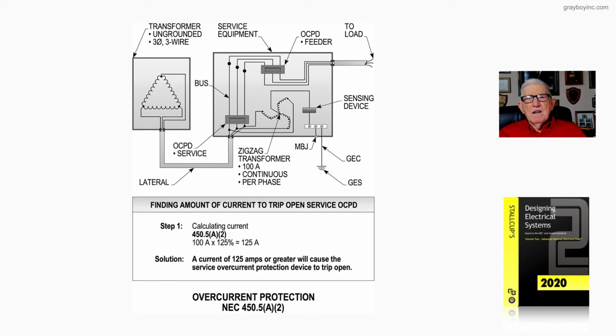But now, kind of reviewing our illustration, 20-13. Then we have the transformer listed there and shown as ungrounded 3-phase, 3-wire. And it's routed over to the service overcurrent protection device that would be located in the enclosure as you see in the illustration. And then you'd have your bus going up, and we would have the service equipment and have an overcurrent device for the feeder routed out to the load. And then notice the zigzag auto transformers connected into the supply side of that overcurrent protective device for the service connected in as shown. Then we're grounded, as you see, to a proper earth ground that we would select from 250.50 and 250.52 of the code, install by 250.53 of the code.